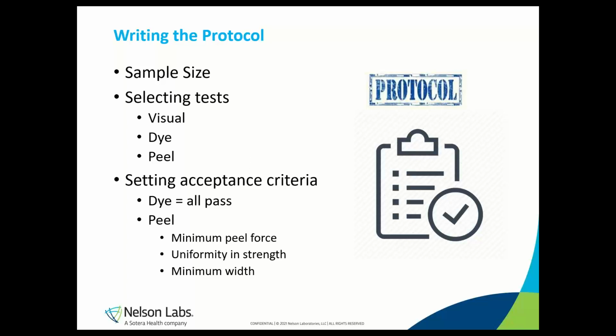We will verify the samples are continuous by seal integrity testing, and we will verify the seals are sufficiently strong by seal strength testing. The sample size for testing needs to be based on statistically valid rationale per the guidance in ISO 11607. We did cover sample size in more detail in the packaging validation webinar on ISO 11607 Part 1, and we also covered more details on the test methods that we're using for the sealer qualification in that Part 1 webinar. So we won't go into those in depth in this one.